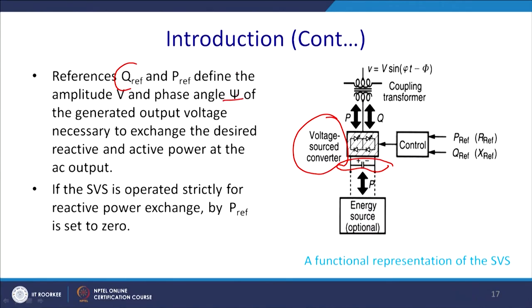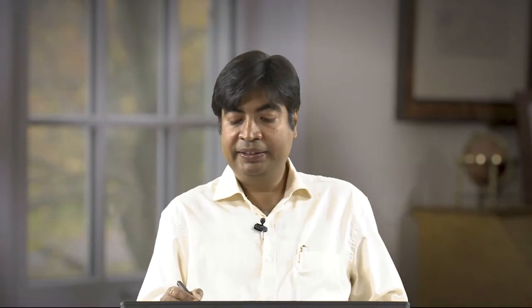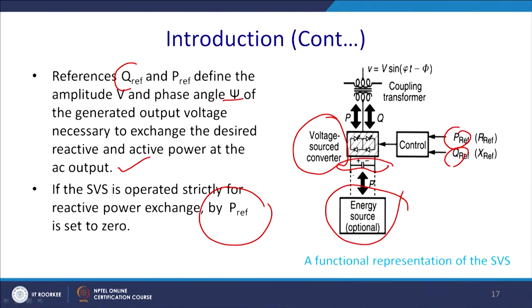The reference Q_ref and P_ref define the amplitude V and phase angle ψ of the generated output voltage necessary to exchange the desired reactive and active power at the AC output. If the SVS is operated strictly for reactive power exchange by setting P_ref equal to zero, no storage element is required. The voltage V = V sin(omega-t minus phi) is stepped down via a coupling transformer to the level where semiconductor switches can operate.